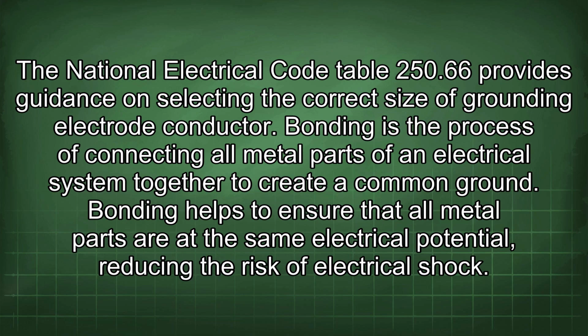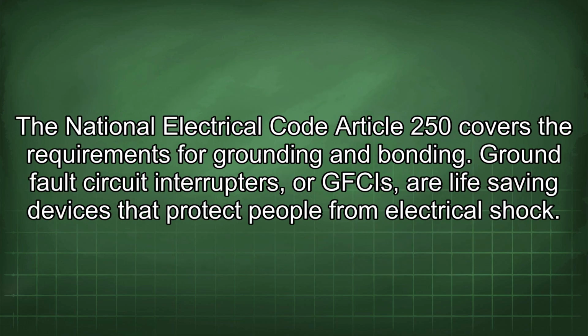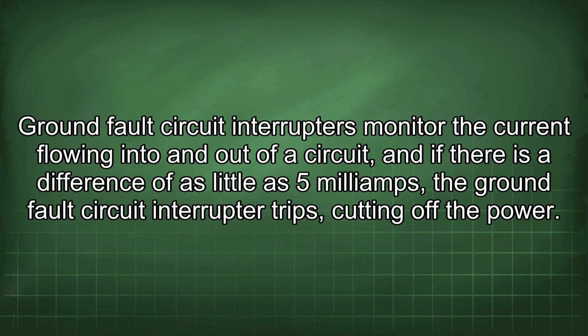Bonding helps to ensure that all metal parts are at the same electrical potential, reducing the risk of electrical shock. The National Electrical Code Article 250 covers the requirements for grounding and bonding. Ground fault circuit interrupters, or GFCIs, are life-saving devices that protect people from electrical shock. Ground fault circuit interrupters monitor the current flowing into and out of a circuit, and if there is a difference of as little as 5 mA, the ground fault circuit interrupter trips, cutting off the power.